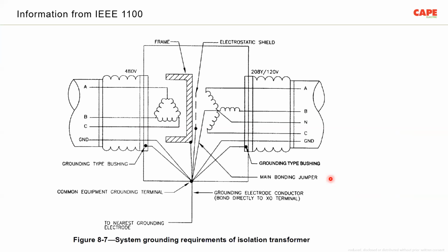We know that we generally use isolation transformers. Every electrical engineer working in industrial and commercial premises and larger buildings always says, "I need a separate neutral earthing. I have an isolation transformer, it requires a separate neutral earthing." Actually, there is nothing like a separate earthing in electrical engineering. Only in the case of a TT system can you have a separate, electrically isolated earth electrode. Otherwise, in your building, in an installation, all the exposed and extraneous conductive parts must be interconnected.